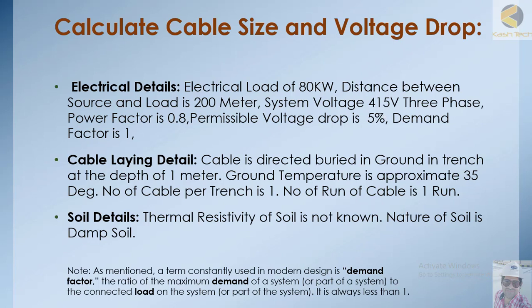We need cable installation details because there is a correction factor depending on the installation method. We must calculate the installed current carrying capacity. A manufacturer provides a base current rating, but if the cable is installed underground or in a tray, the rating must be multiplied by a derating constant. Soil resistivity and soil condition — whether damp or dry — are also important. Greater burial depth reduces current carrying capacity, while damper soil increases it.